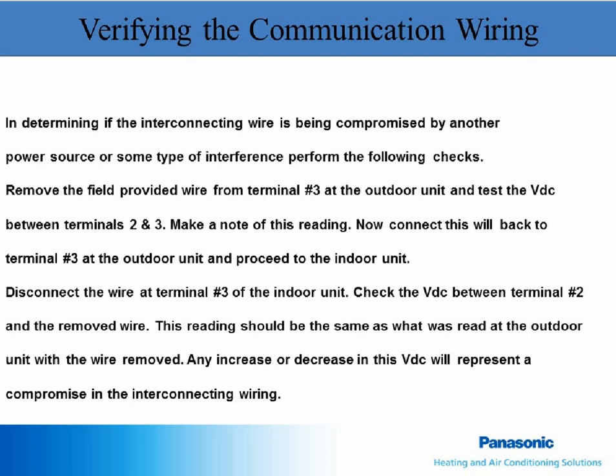At the indoor unit, remove the wire on terminal 3. Take a DC voltage reading between the wire and terminal 2 and write it down on a piece of paper. The voltage reading at the indoor unit and the outdoor unit should be very close to each other. If it is high or low, this is an indication that you're having communication problems.